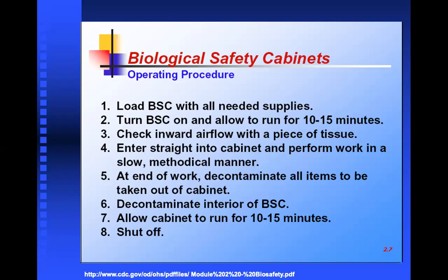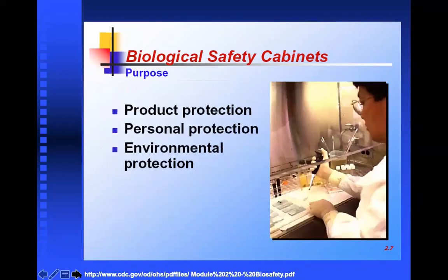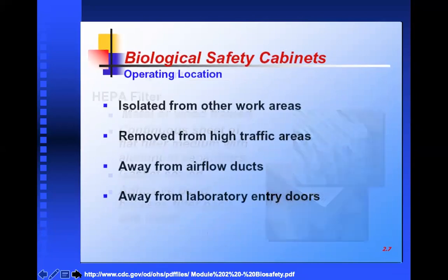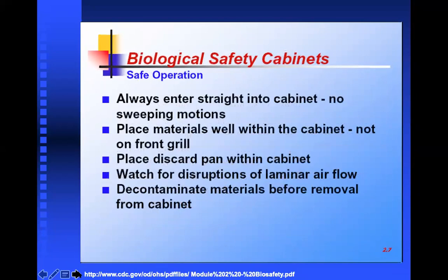In some cases, laboratory workers are in a hurry, so they miss steps 2 and 7, these two points, that are very important. And usually in biosafety cabinets, when you stop working and complete your job, shut down the window, and if the window is UV protecting, otherwise you can use a UV protecting screen, and then turn on the UV light, so that if any microorganism remains, it is killed. It needs around 20 minutes, and after 20 minutes another person can work, otherwise contamination would be a big problem. So to avoid contamination, we have to do such a thing.